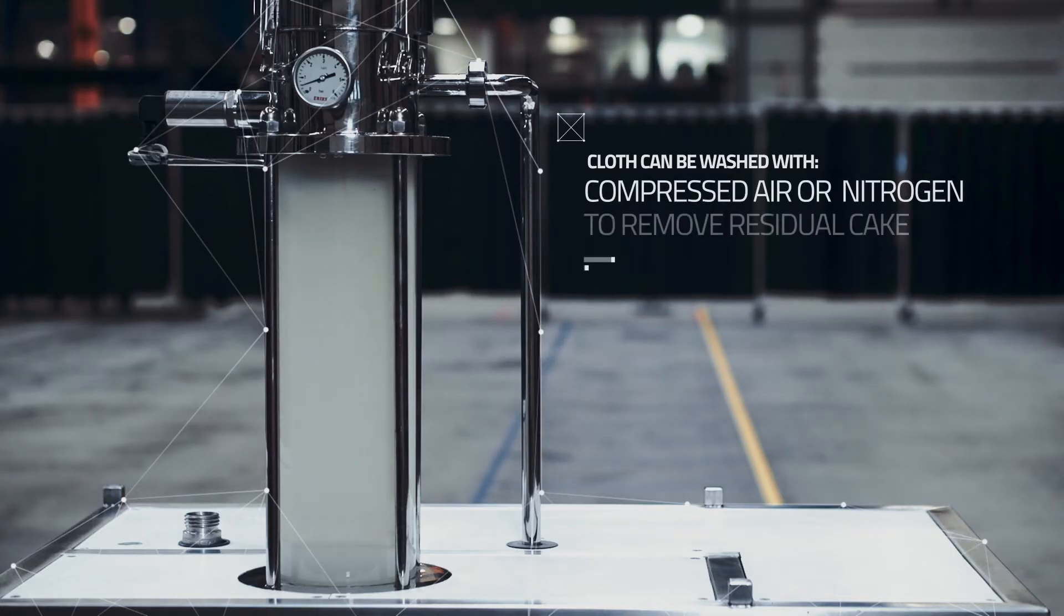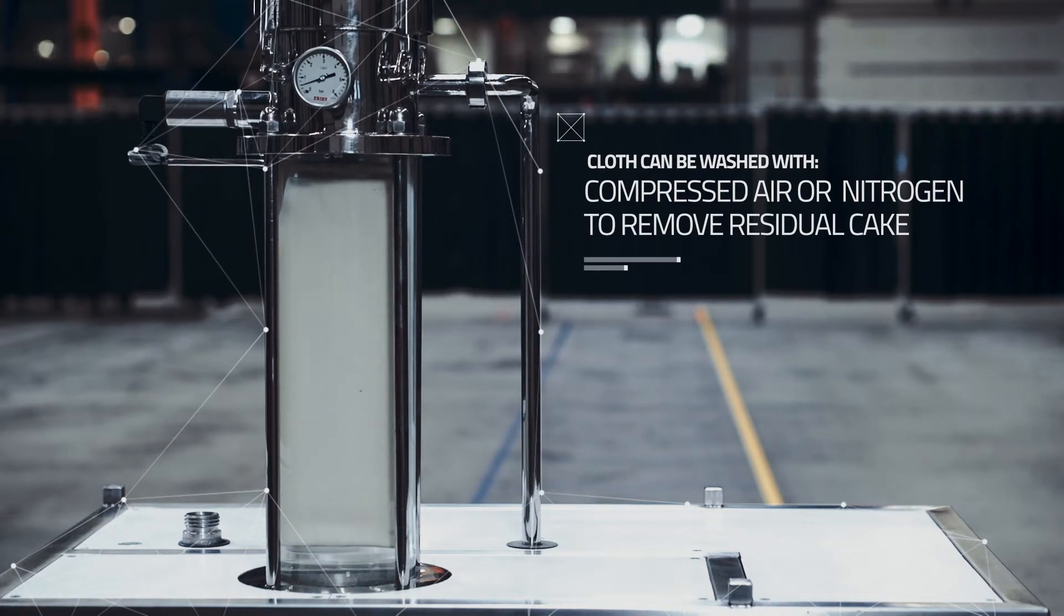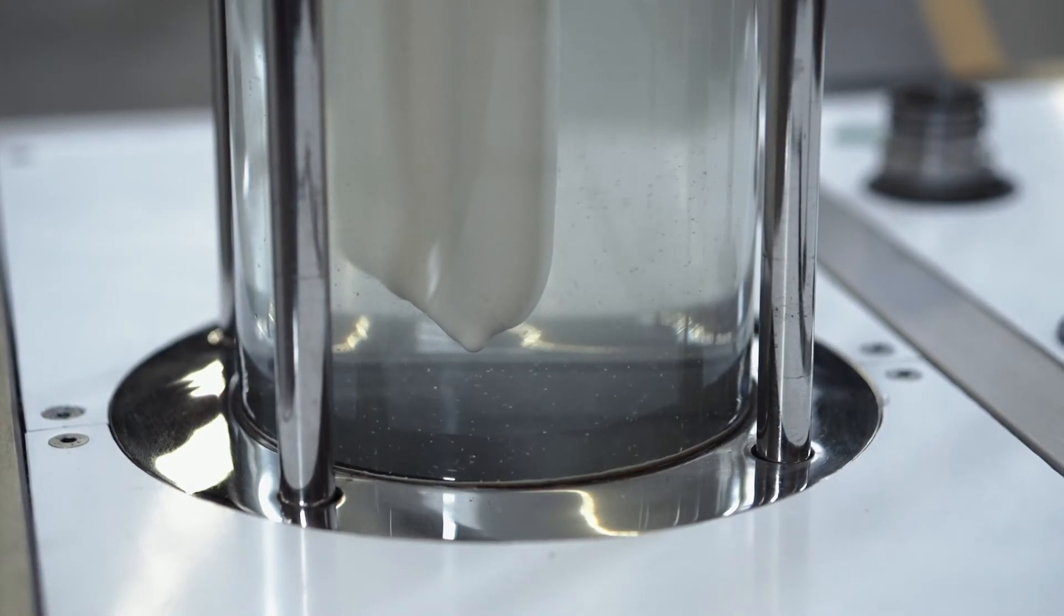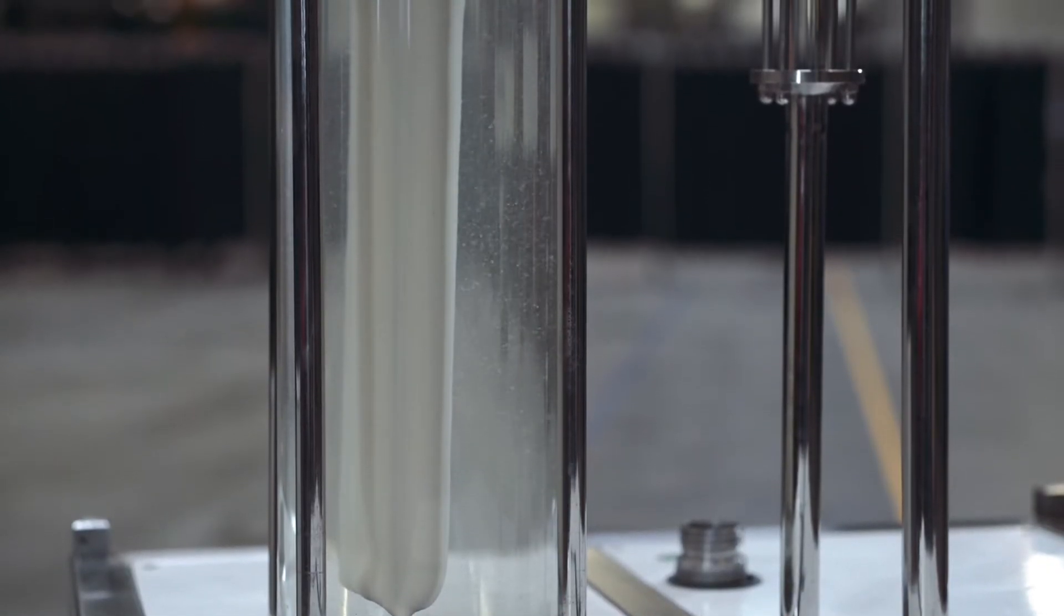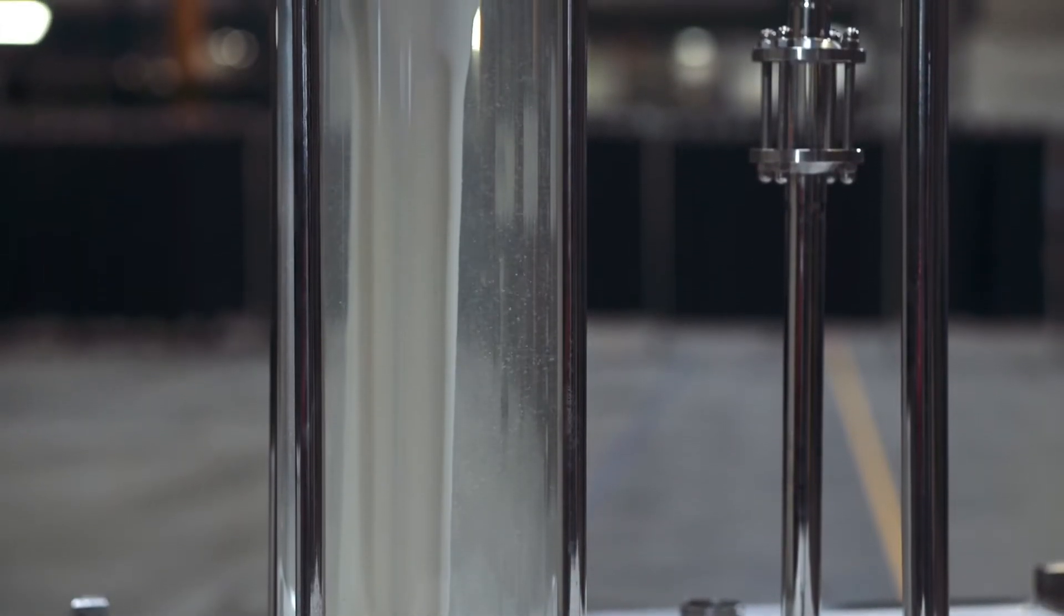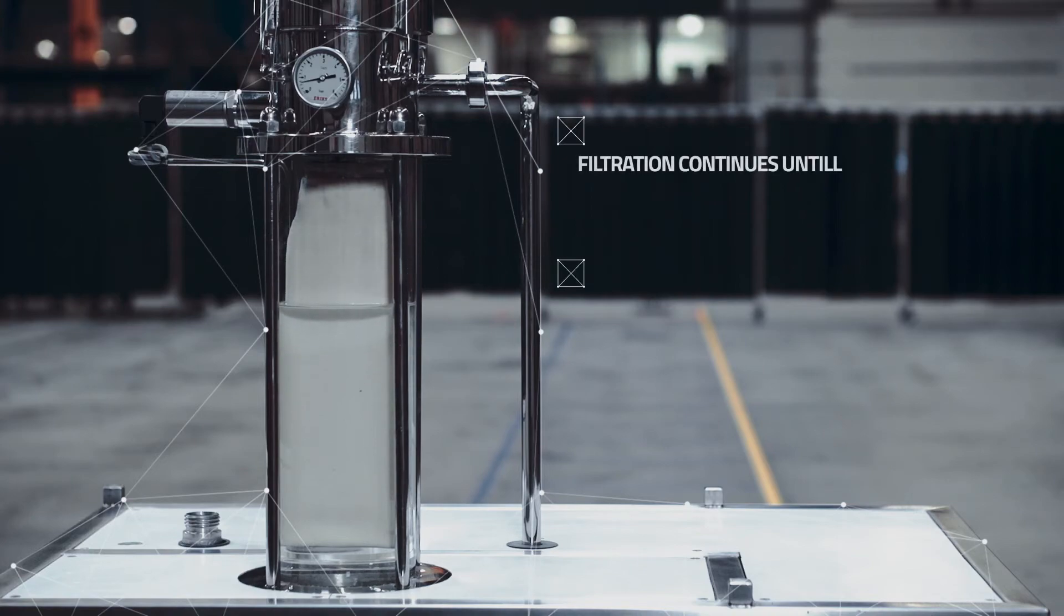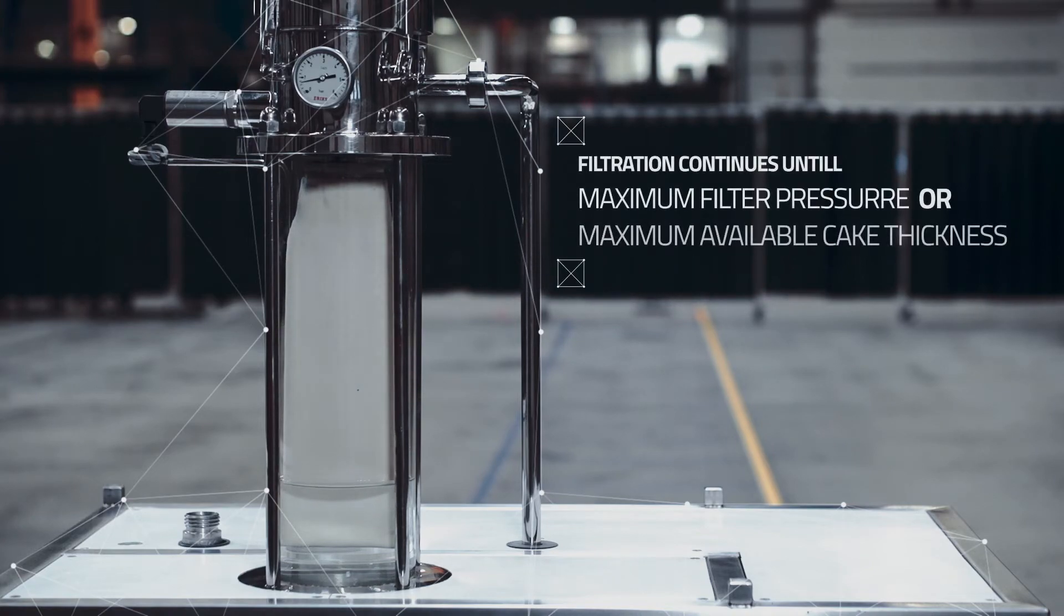Prior to filtration, the cloth can be washed with compressed air or nitrogen to remove residual cake of previous filtration runs. The filtration continues until the maximum filter pressure or the maximum allowable cake thickness is reached.